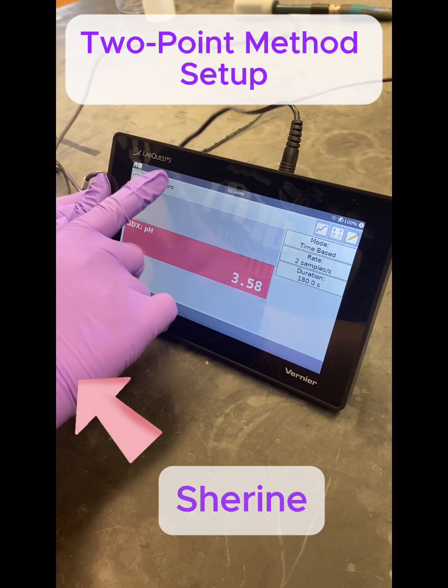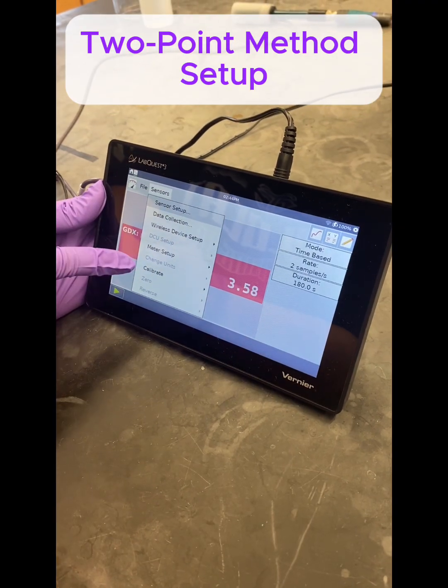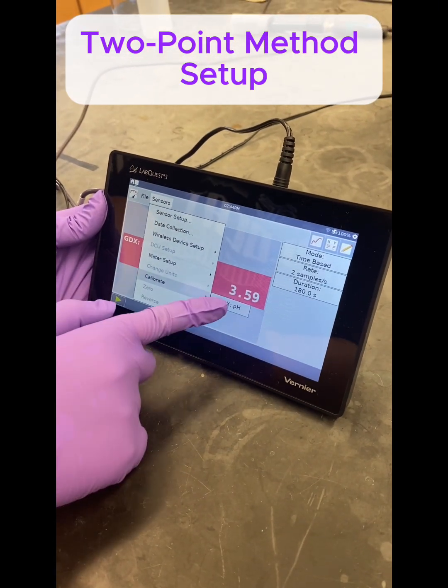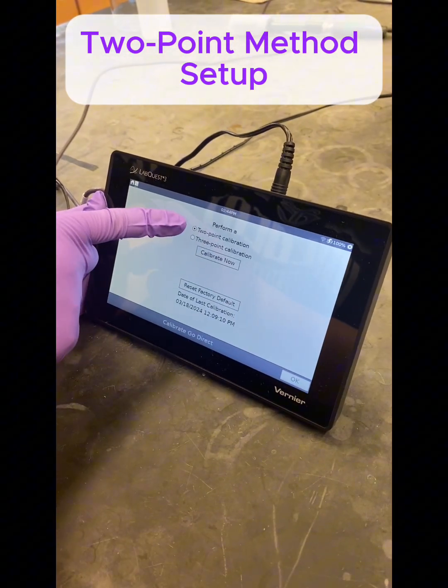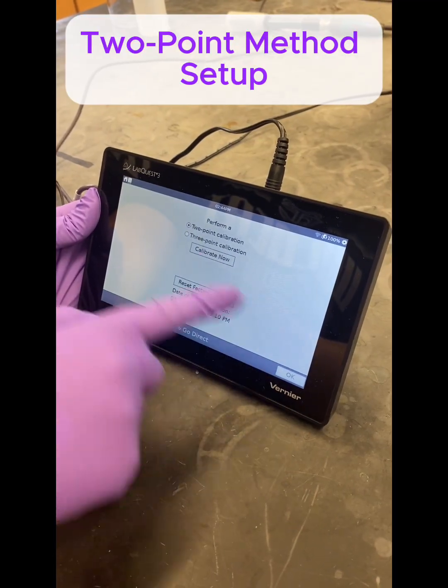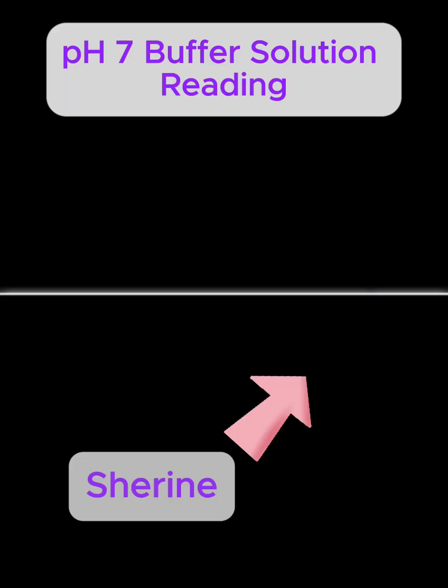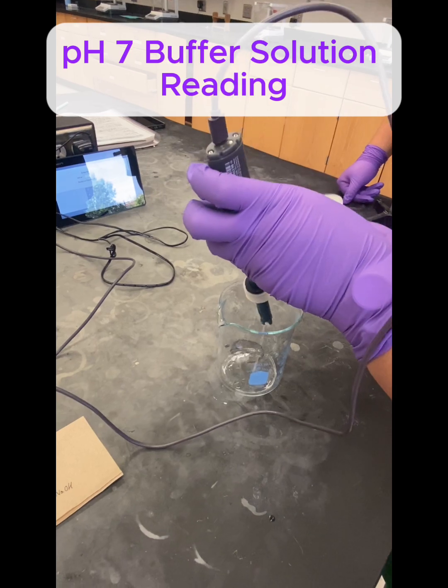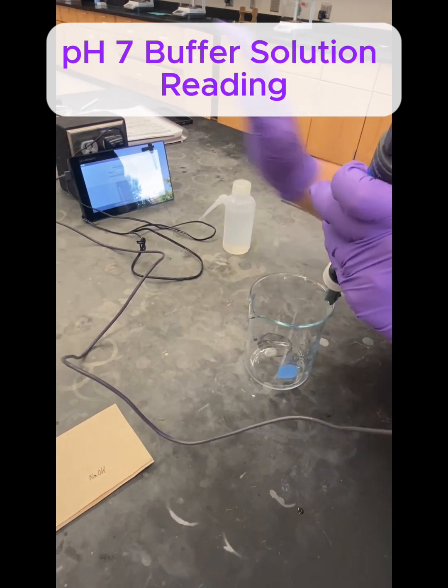We begin calibrating the pH meter using a 2-point method. This involves placing the probe in pH 7 and pH 4 buffer solutions and entering these values into the meter to get accurate measurements. You will then rinse the electrode with distilled water and lightly dry it using a Kim wipe.